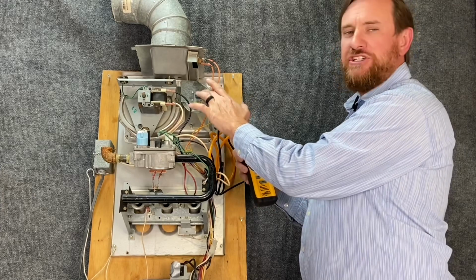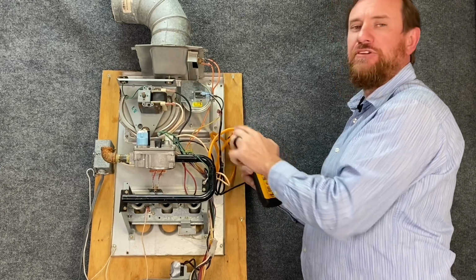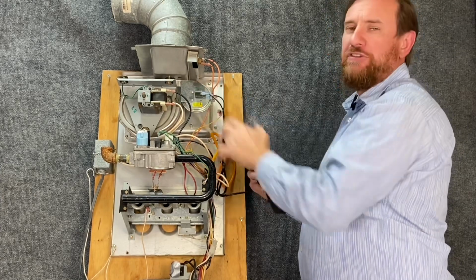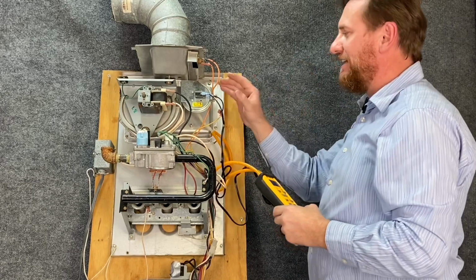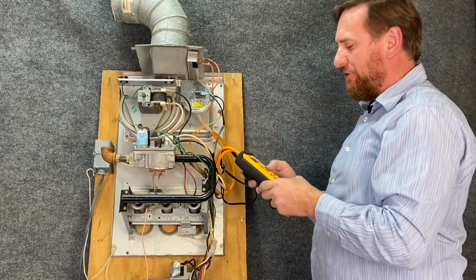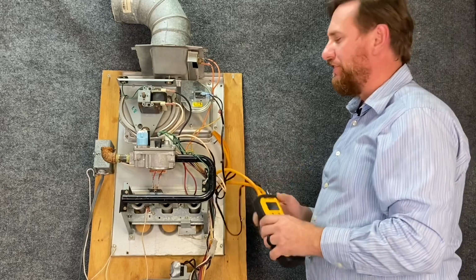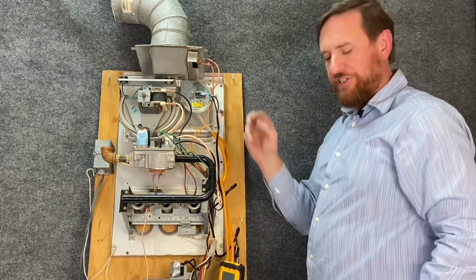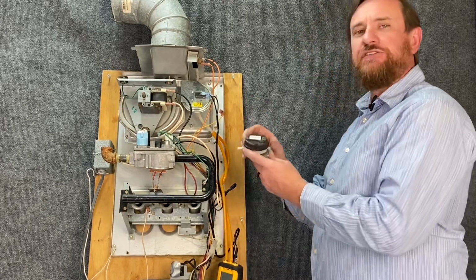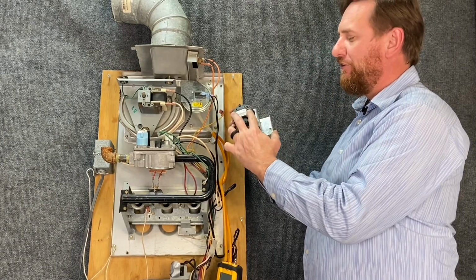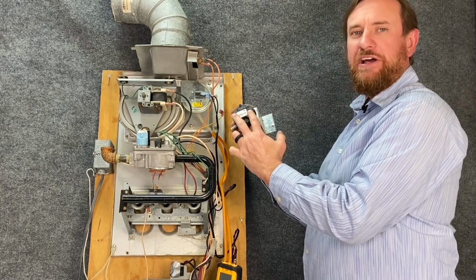So know that my switch is good. It closed at 0.25 inches of water column, and that's what the switch is designed for. So my switch is working 100% correct. So it's another way of checking the pressure switches. Now most of these pressure switches are NO. NO stands for normally open. So if I check these two, they're normally OL, infinite resistance.